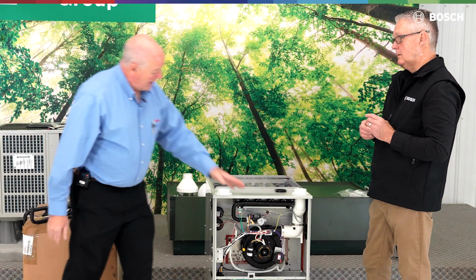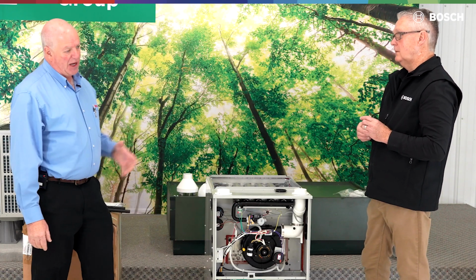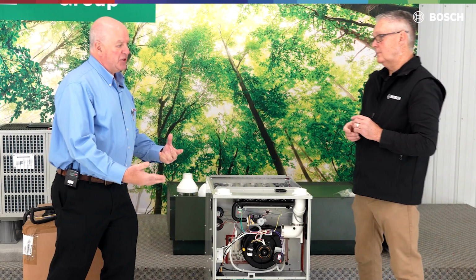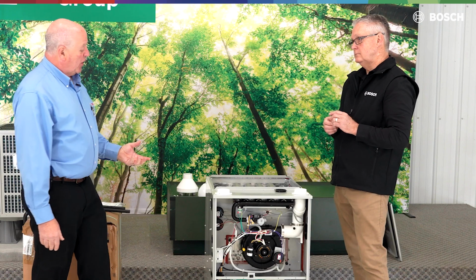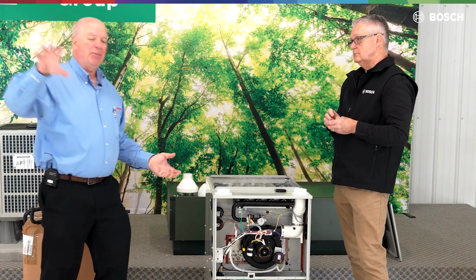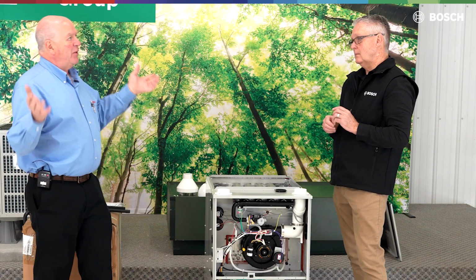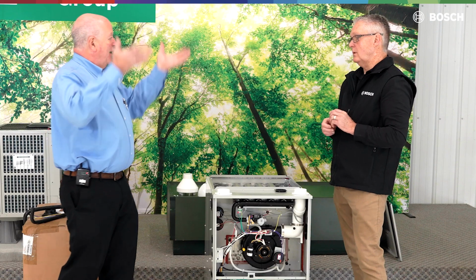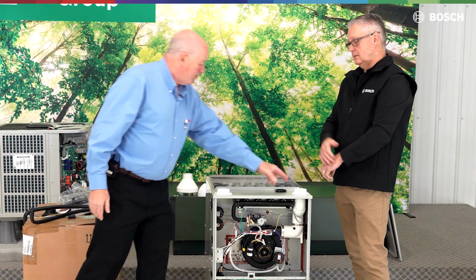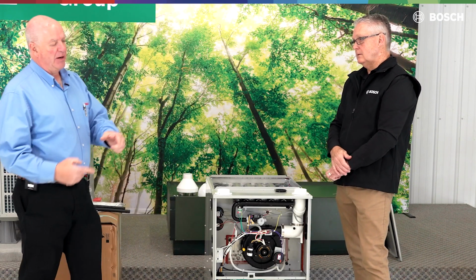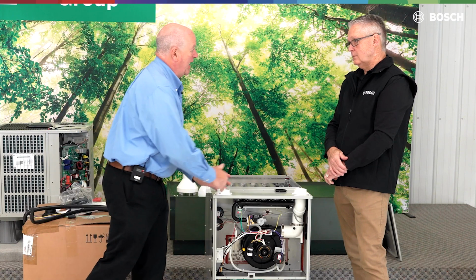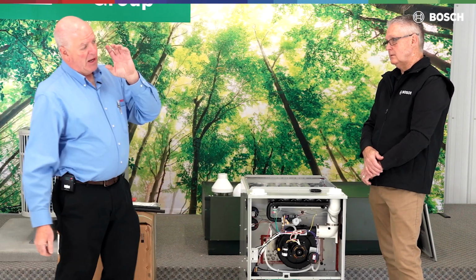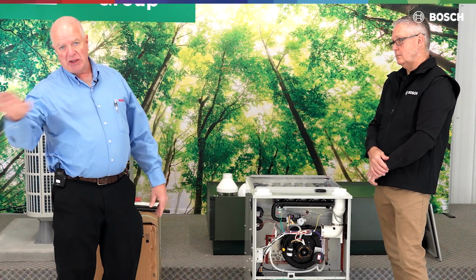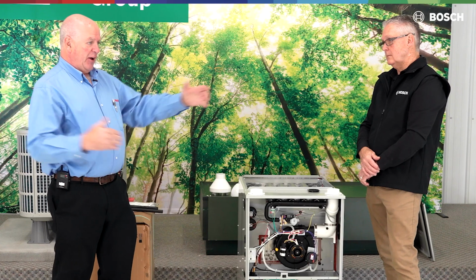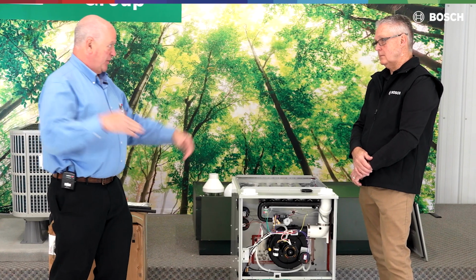And so this blower has to overcome that reverse pressure coming in. Sometimes in attics, if these are vented into an attic or installed in an attic and you have a fresh air intake coming out of the attic, that ridge vent, when it gets warm up there, pulls a lot of air up to that attic, and you've got a lot of negative pressure being pulled through here that has to overcome. A lot of times you're better off, if you can, to put 2 pipes on that system, run them both out the east wall, both out the west wall, whatever side you're on, not on opposite sides, so we don't get the air blowing through that unit.